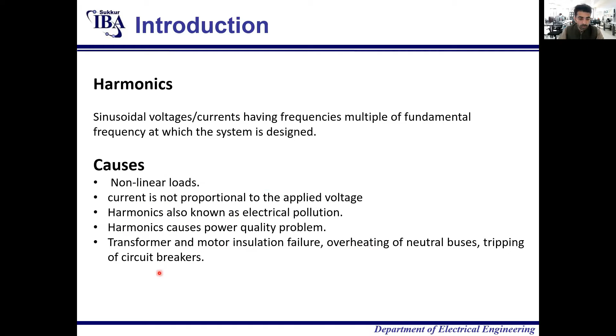So why are those harmonics produced? What are its causes? The causes are non-linear loads. It can be power electronic components, rectifiers, and other power electronic compensating devices which create these harmonics. This happens because current is not proportional to the applied voltage. Harmonics are also known as electrical pollution. Harmonics cause power quality problems, transformer and motor insulation failure, heating of neutral buses, and tripping of circuit breakers.